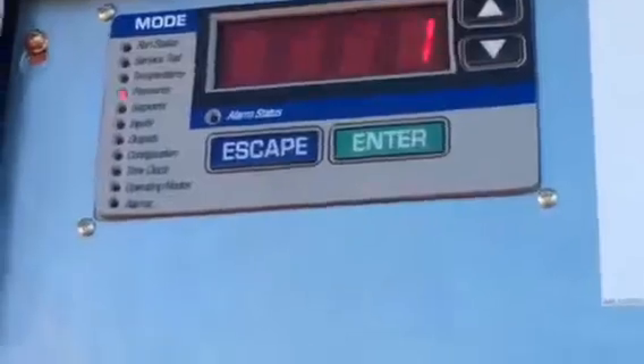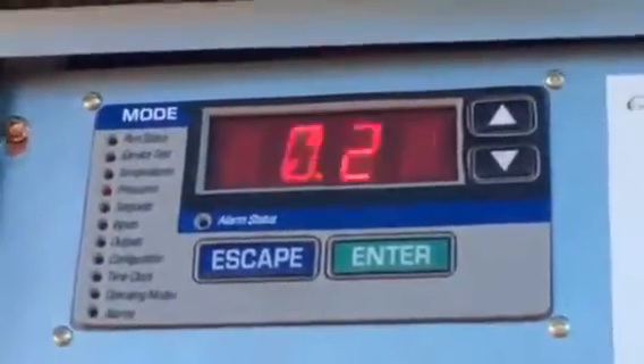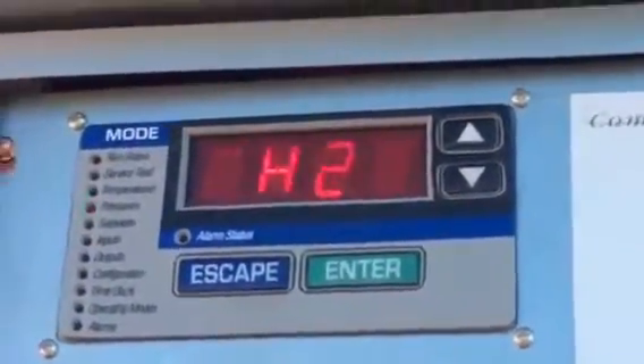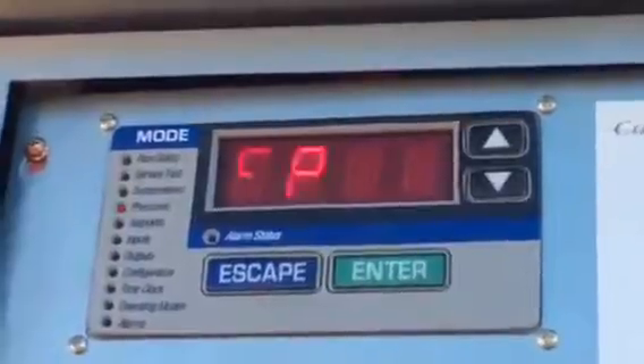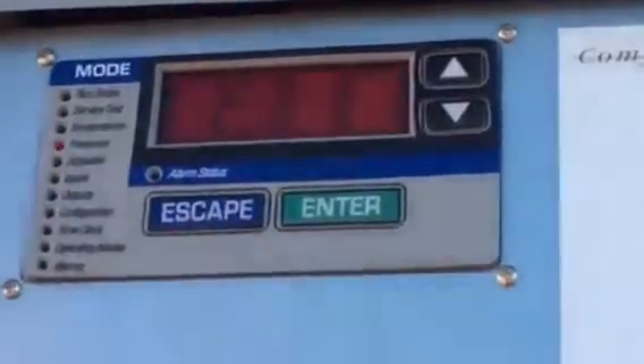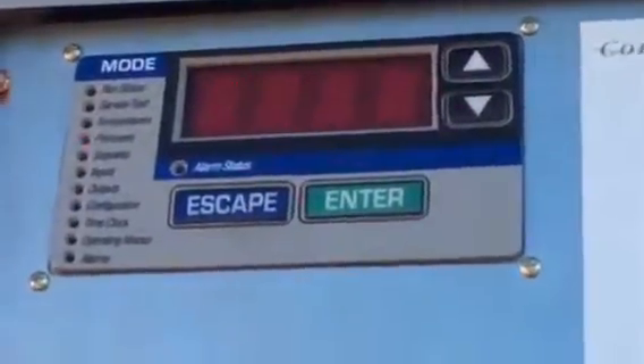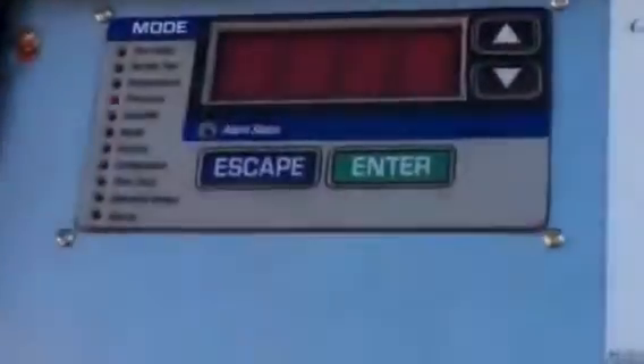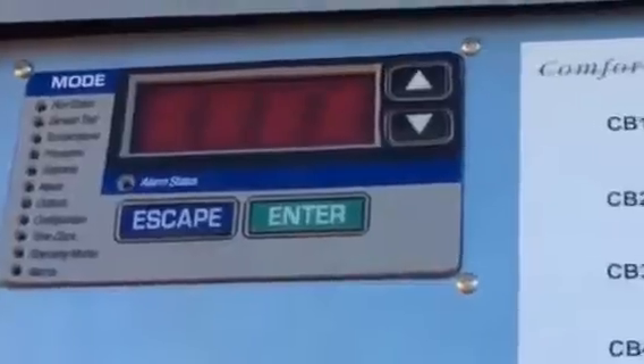So basically right now I know at 32% of speed or 32% of my set point, I'm making 0.22 inches of static. So basically most all the boxes down there are closed and nobody really needs any cooling, so things are shut down. If I ever get lost with the marquee or the navigator, just hit escape until the display goes blank. It'll back you out enough levels to like the root or top level.